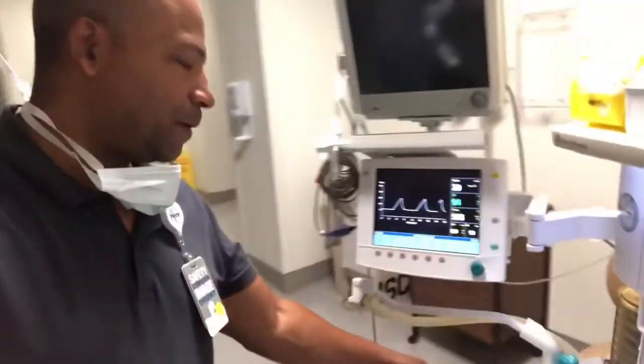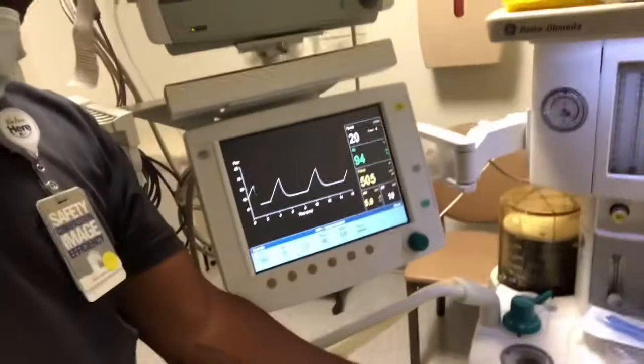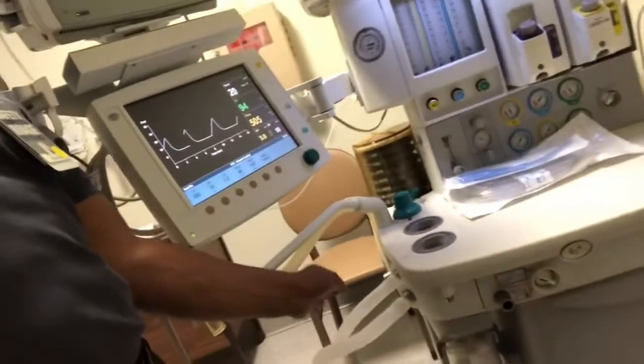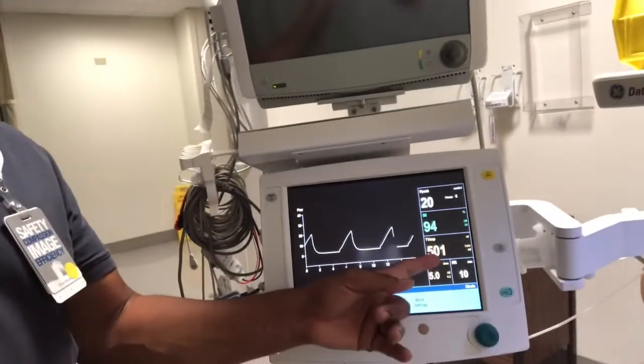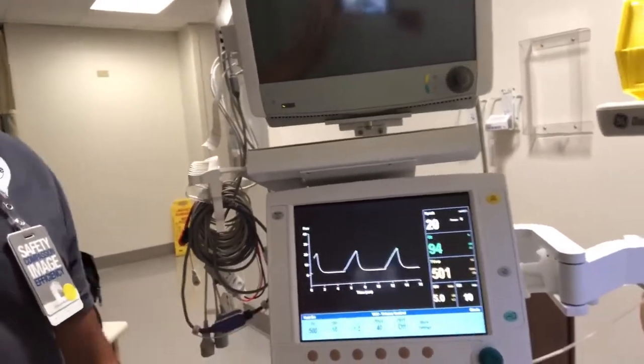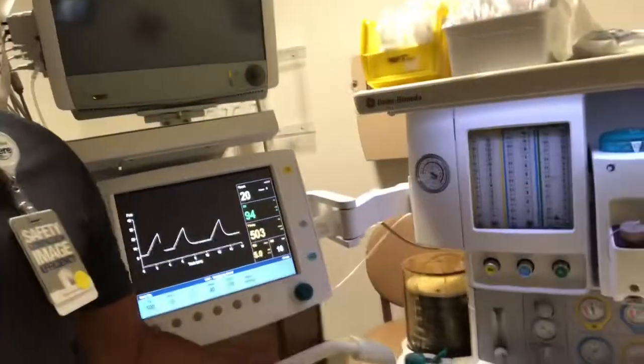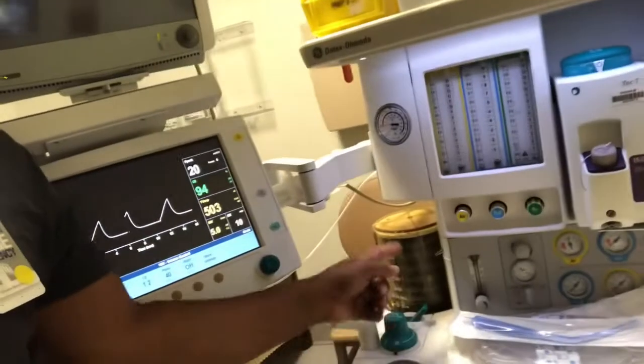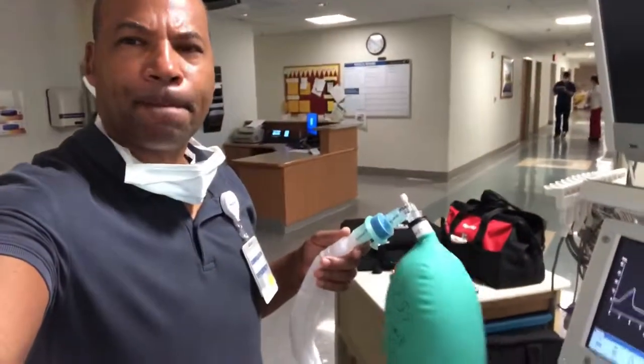All right, so I got this all put back together, and now we have the Aspire View here. We see it cycling and functioning normally as it should once we put the pneumatic breathing system back in. It's all cleaned up, and that's what we want. It's a normal function operation, as we can see here in our display. Exhale volume, rate, oxygen. We see our bellows doing what they're supposed to do. No leaks. I think we got it.